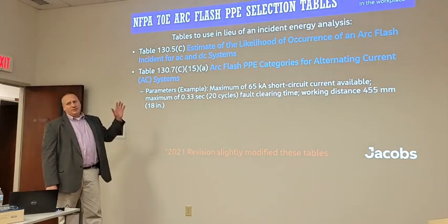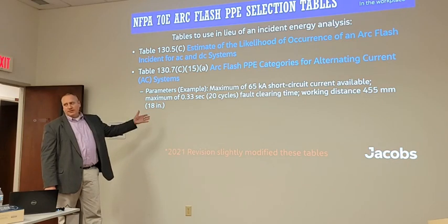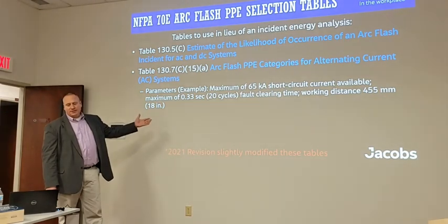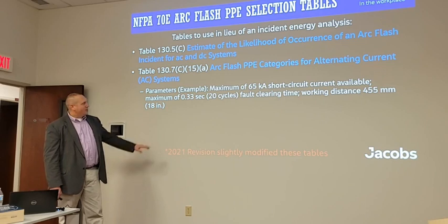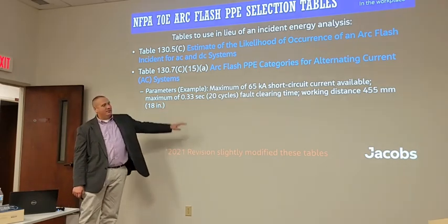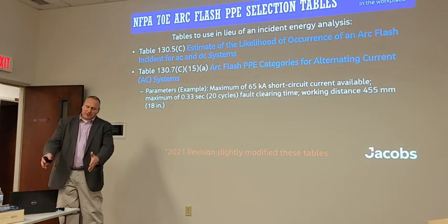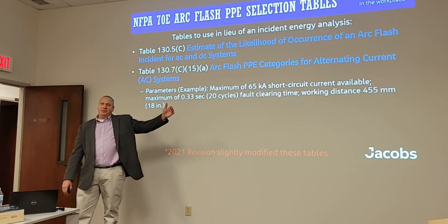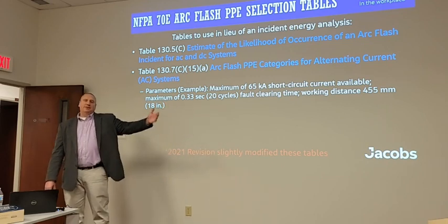Well, the challenge is this is really for somebody that's out in the field and there's no sticker on the equipment. How do I make a decision? In the field, most of the time, you're not going to know what the rating is for the equipment. The more challenging thing is the clearing time. The clearing time is not even the equipment you're working on, that's the equipment upstream, the upstream protective device. And how do you know the clearing time from that?